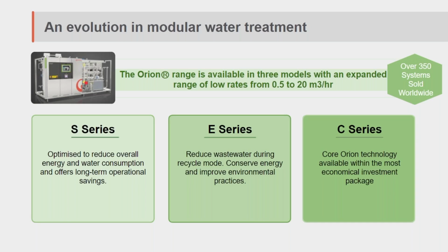In terms of flow range, these units are available from 0.5 meter cubed an hour up to 20 meter cubed an hour. We recently supplied a site in Australia for 3 Orion 20,000, so they're 20 meter cubed an hour each, producing a total of 60 meter cubed an hour. So we have a range of about 7 to 8 unit sizes within this product.